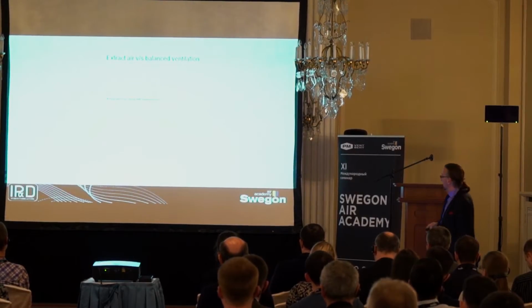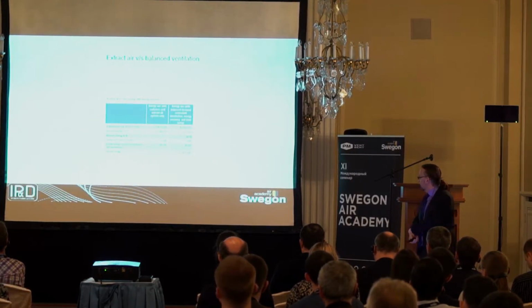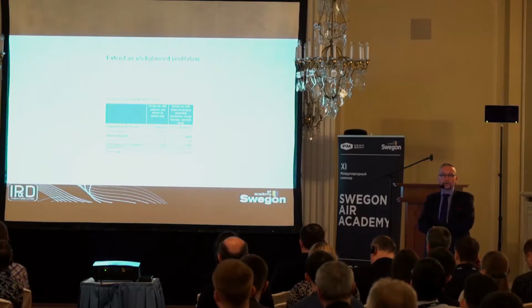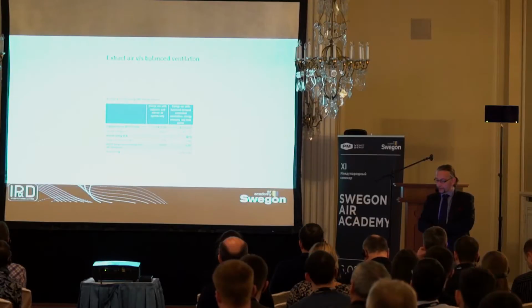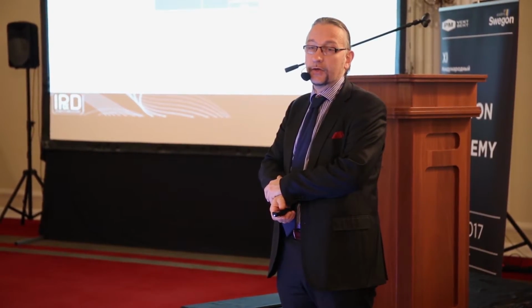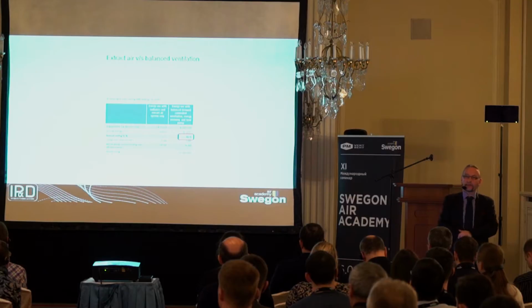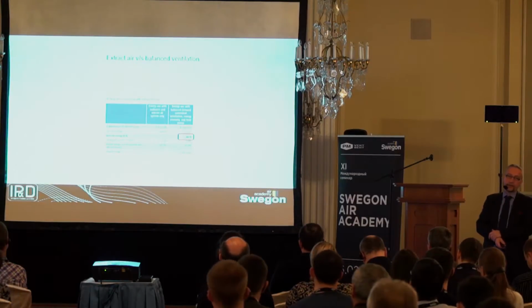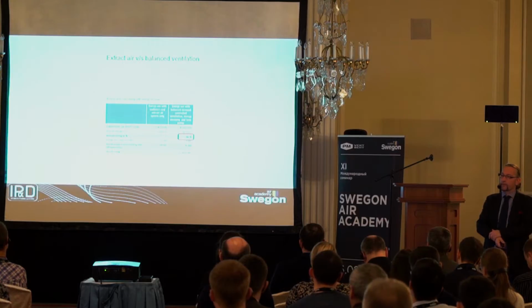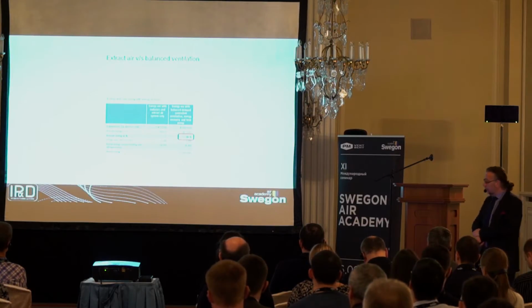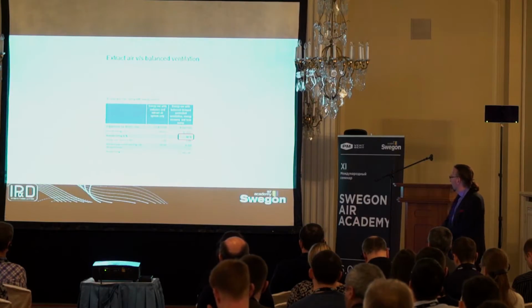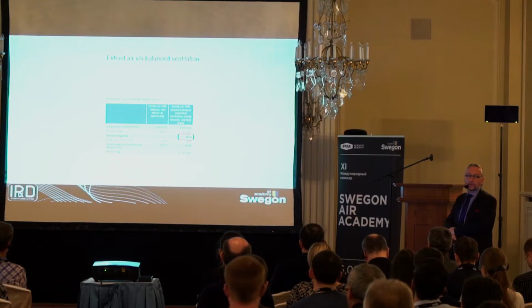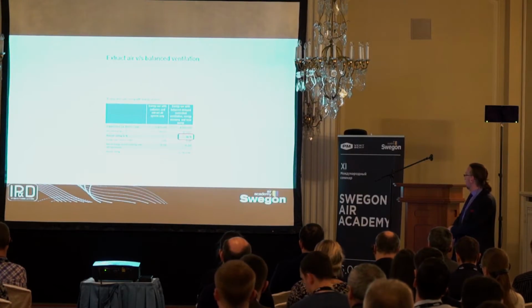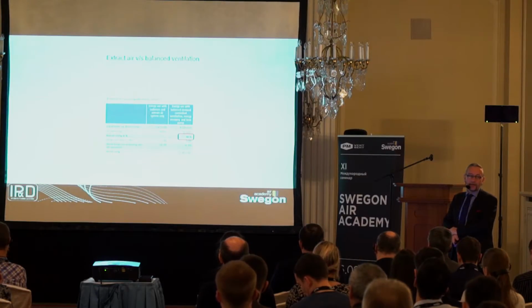Now if we look at the energy cost for this kind of system: this is a big sheet comparing the energy use of an extract air system with a system with balanced air volume and energy recovery. What you see is the energy saving is 66%—two-thirds of the energy is saved by having a balanced air volume system with recovery. That's quite a bit of money. In this apartment block of 100 apartments, you have 72,000 euros of annual saving every year. That is an extensive saving.